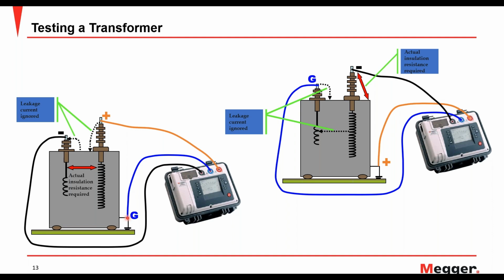The reason why I'm doing that is I want to ignore any leakage current that is going on the surface of the transformer, that is on the tank. Anything related to tank, I don't care about. I just want to see how the insulation resistance reading is between my high to low winding. So that's all I care about. I don't care about the surface discharge.